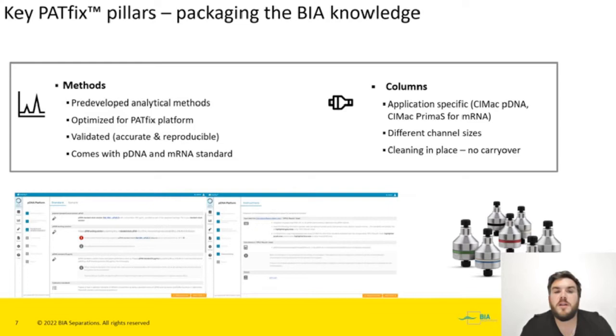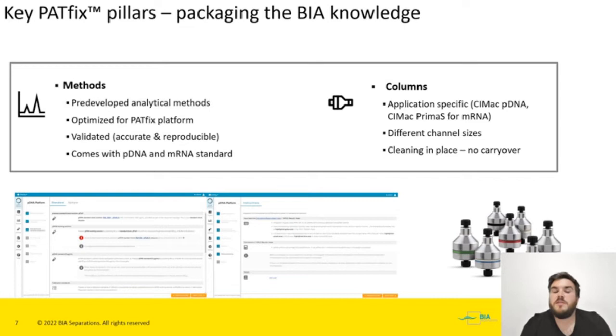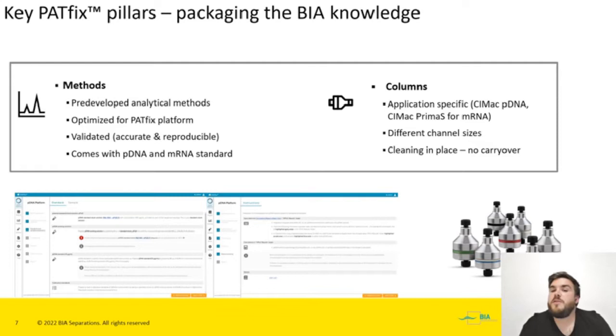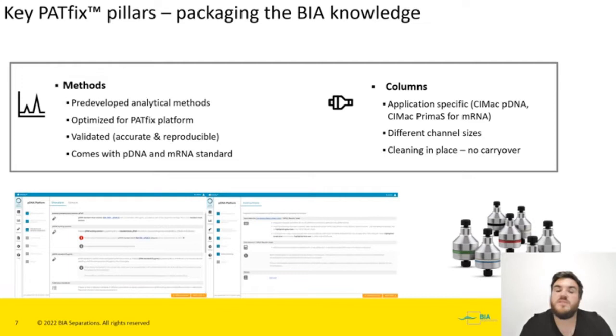Our PATfix analytical platforms come with pre-developed analytical methods specially optimized for the PATfix platform. The methods are also validated, which ensures accurate and reproducible analytical results. We also developed pDNA and mRNA chromatographic standards for quantification of these biomolecules. The platform comes with pre-selected, application-specific analytical columns — for pDNA analytics we use the CIMac pDNA column, and for IVT monitoring for mRNA production we use the PrimaS column. The columns come with different channel sizes, enabling analysis of biomolecules of different sizes and cleaning in place to assure no carryover.